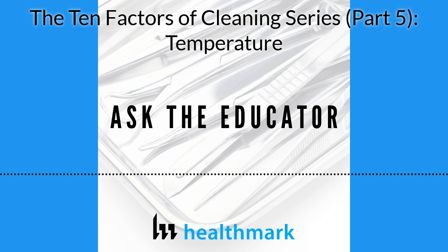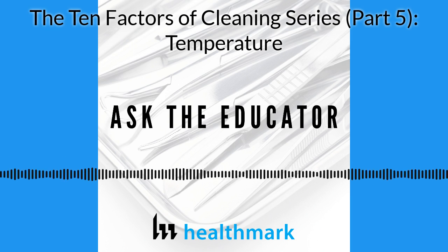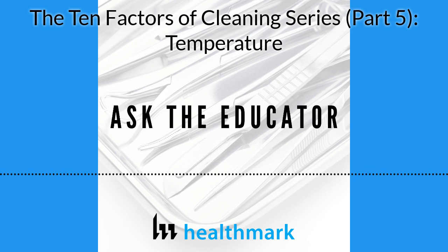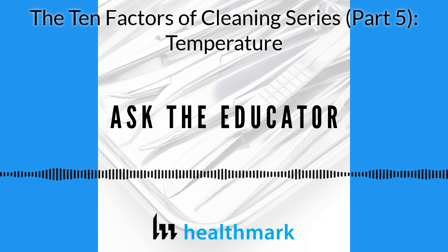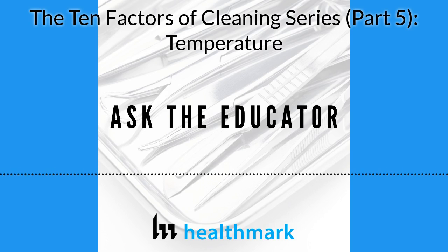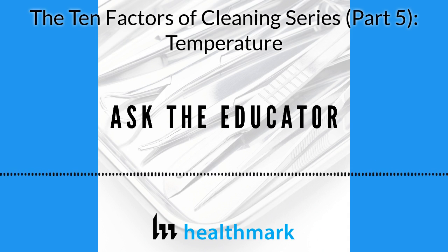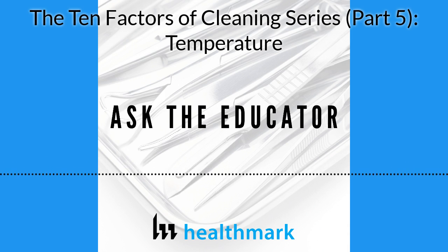And think of your cleaning solutions, whether it's enzymes or detergent, alkaline, they have optimal temperatures and they work differently. Most enzymes, Kevin, and again, we're talking in general, they like temperature around 120. If they're in too cold of water, they aren't as active and work. And then if it gets too hot, they get destroyed or don't work at all. The other thing is, think of your detergents or your alkaline solutions. They like temperatures that are hotter, and that's very, very important.